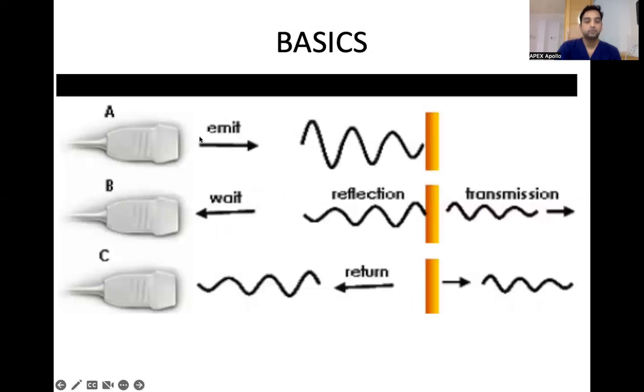The tip of the probe contains many piezoelectric crystals. These crystals, when activated by an electric current, emit sound waves. Some of the sound waves are reflected, some get absorbed, and some get refracted. The sound waves which return to the tip of the probe are processed and ultimately displayed as an image on the ultrasound console, which the operator interprets.